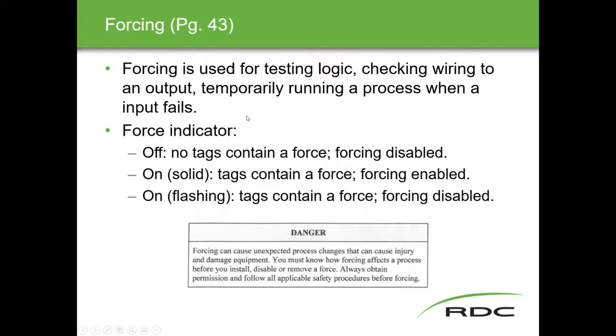Forcing. Okay, forcing is used for testing logic, checking wiring to an output, or temporarily running a process when an input fails. You'll have a force indicator. Again, depending on your software, it's a different type of indicator, but there'll be a little indicator in your programming software that tells you if you've got something that is forced.